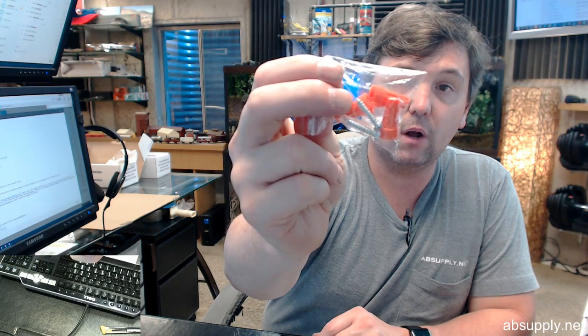Now, the next paragraph in the installation instruction, and by the way, again, wire nuts are included. The next paragraph in the installation instruction talks about testing. The summary of testing basically says once a month, test it for 60 seconds. Hold the test button down. Your lamps should be illuminated for 30 seconds, not 60. Lamps should be illuminated for 30 seconds.